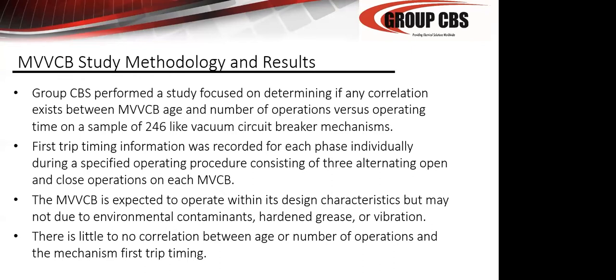Finley, we do have a question that has come in. Sure. If the mechanism is operating at the correct speed, and we have studied maintenance consumables, meaning the cleaner, the lubricant, the grease, and has very limited fault operation, then cannot the life be anything up to 40 or 50 years, particularly if the switchgear has an internal arc classification?